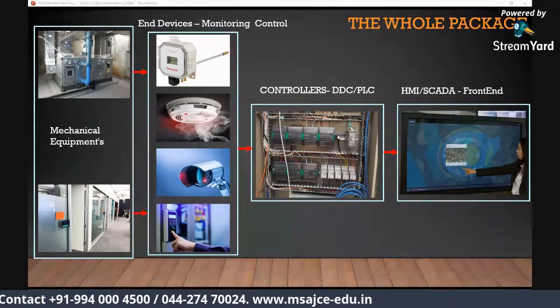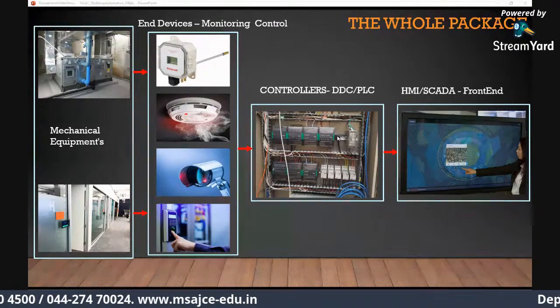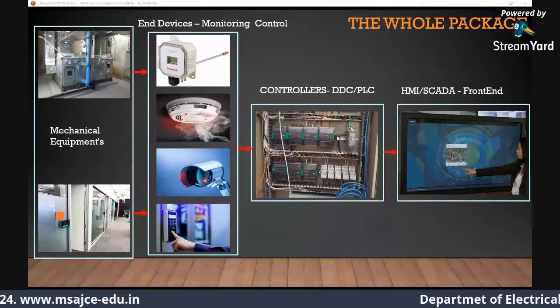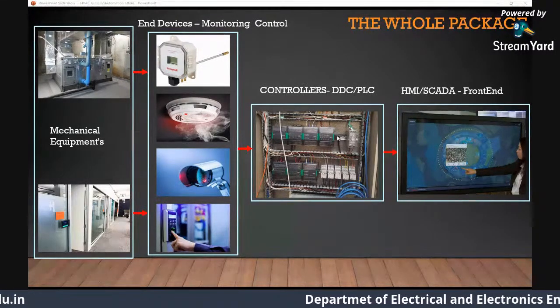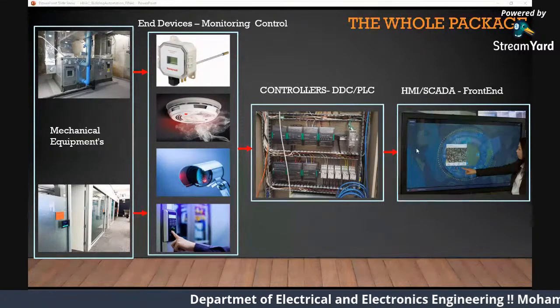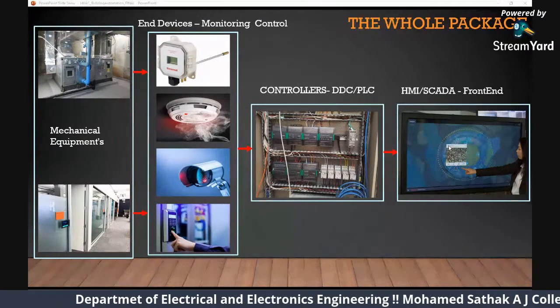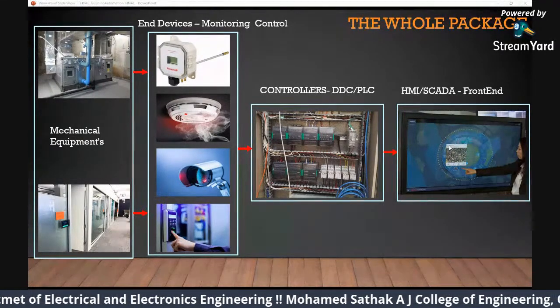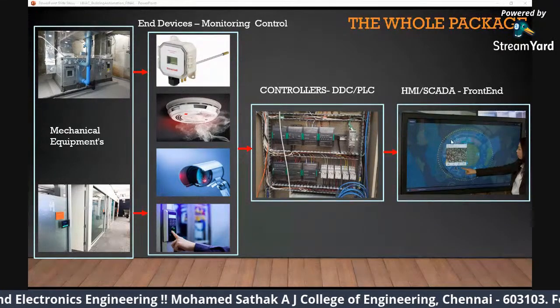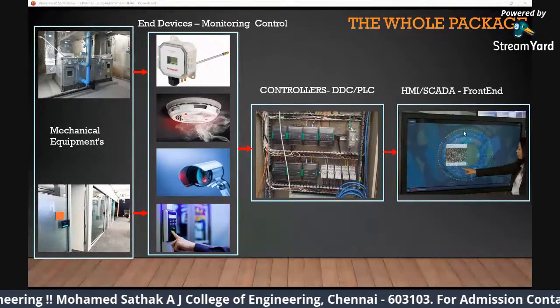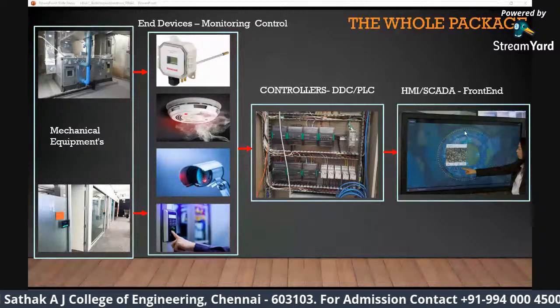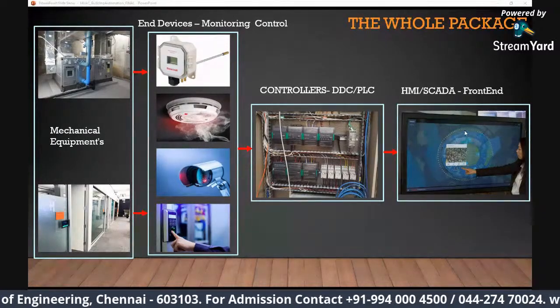All your controllers will go to your output devices, which are your VFDs, actuators for your valves and dampers, relays and contactors for your fans and pumps. Now, this complete thing is being monitored through your HMI and SCADA front end by your operator and engineer. Once everything is installed, commissioned, and downloaded, your front end is your go-to access.